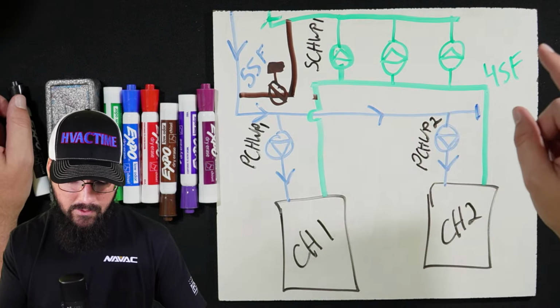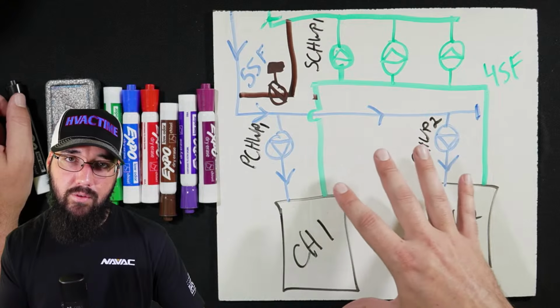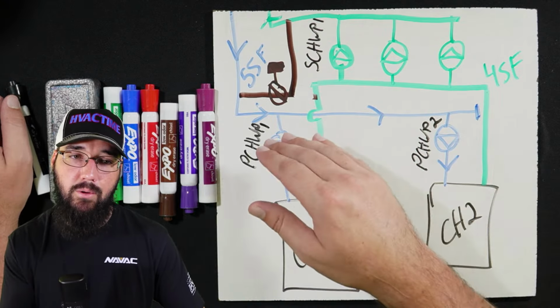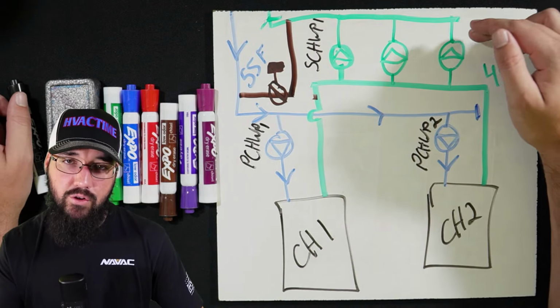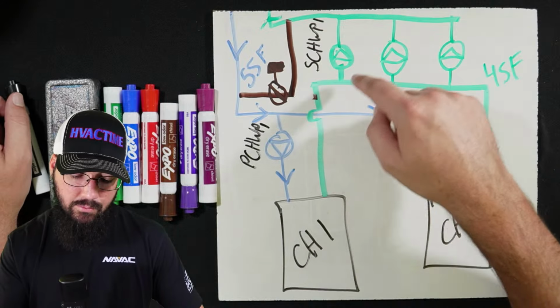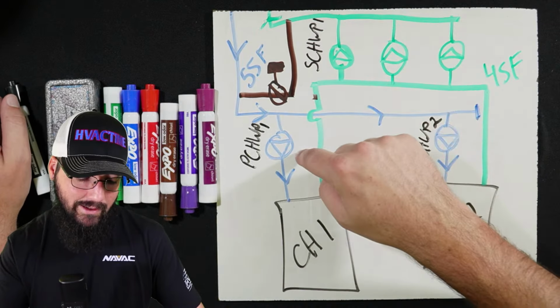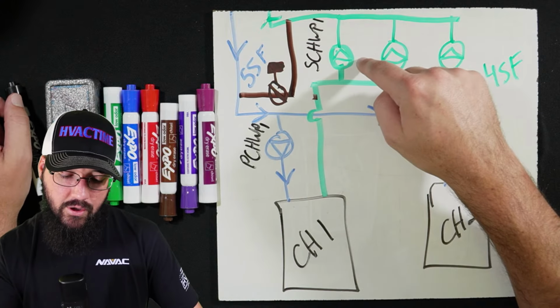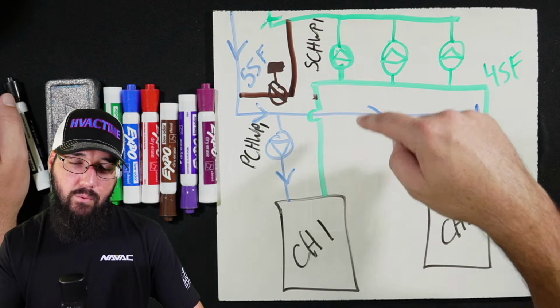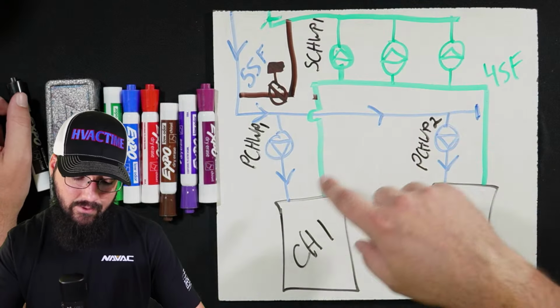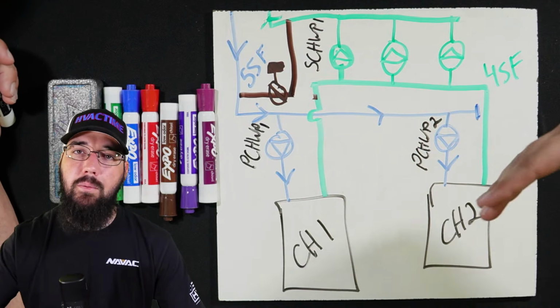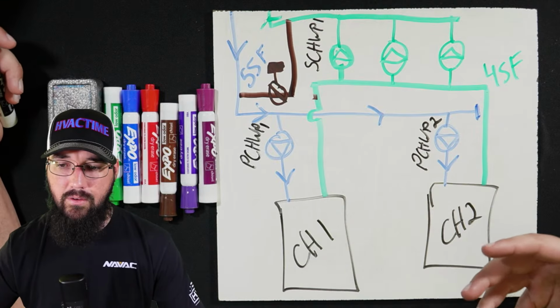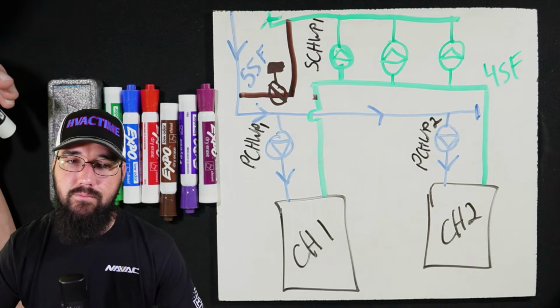So normally, if we're shutting both chillers off, meaning both primaries don't need to run, but we just want to recirculate, then we will end up running at least one of them. We'll at least have primary pump 1 or something run in conjunction with the secondary pumps in order to have flow. If we want to maintain flow on the main loop but not have the chillers online, that is something we will end up doing in that scenario. At least these are from the plants I've seen and worked on. These are the designs I'm familiar with. There may be some other tweaks to this, we run into all kinds of stuff.